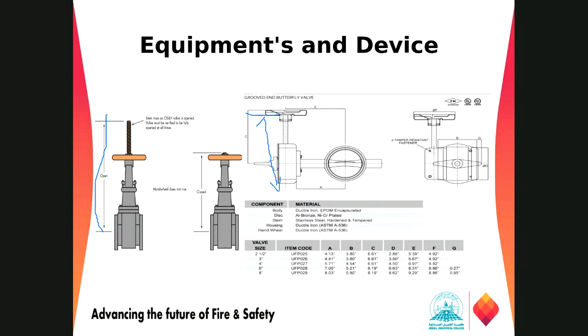Then we have equipment and devices. We have PIVs, which we call the post indicator valve, right? This PIV should be at least 40 feet away from the building, because in case of fire, the fire department team should be able to control the sprinkler risers from here, so that they will not be affected by the building collapse or damage. On the right side we have a wall post.